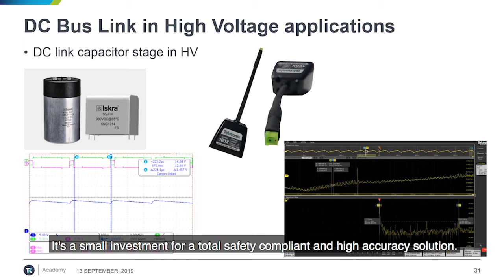So you may need to measure these voltages in a galvanically isolated way, in accordance with your internal safety regulations, and you may need to gauge the ripple on the bootstrap power supply voltage at the high voltage DC link. This is a typical case where the IsoVu probe can easily support you with high voltage tip adapters - a small investment for a totally safety compliant and high accuracy solution.